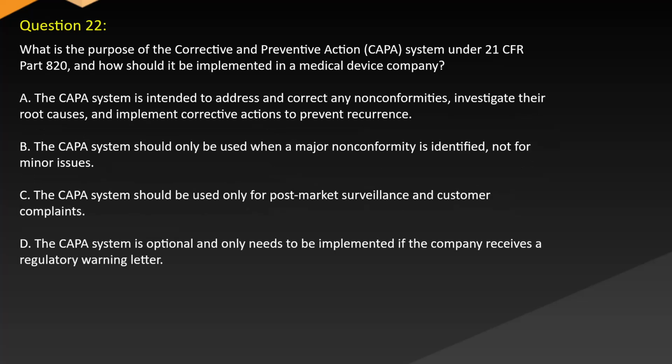Question 22. What is the purpose of the corrective and preventive action (CAPA) system under 21 CFR Part 820, and how should it be implemented in a medical device company? A. The CAPA system is intended to address and correct any nonconformities, investigate their root causes, and implement corrective actions to prevent recurrence.